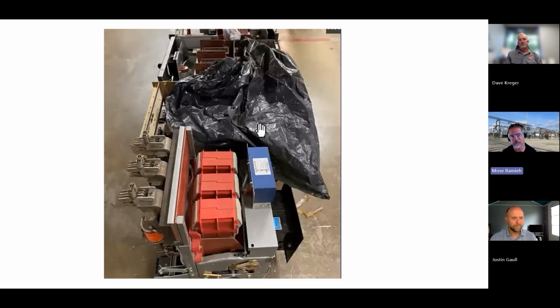And one thing I like to see too, especially when it comes to spares, is a test report included with the breaker, so you actually have documented evidence of the last time it was tested. Obviously it should have a tested-by sticker on there if a company's following standard testing protocols. But once again, if it's going to be a legitimate put-it-into-service spare, you really got to make sure you're taking great care of it so you can grab it off the shelf and do, at a minimum, an insulation resistance test before you put it into service. Just to make sure something hasn't fallen inside there, or once again, mice and rats can do some crazy stuff, and you'll never know they're in there until it's too late.